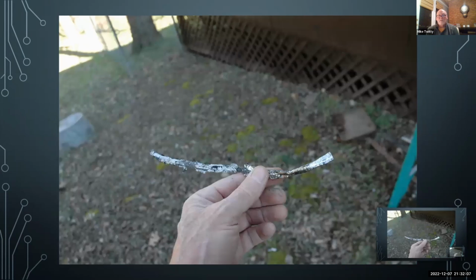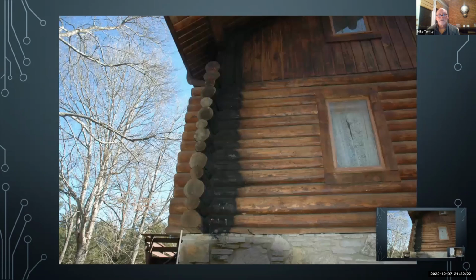The only return path for that neutral current back to the transformer was on the coaxial cable. That's what's left of it. It was traveling on that shield that was carrying all the neutral current of that house back to the transformer, and it melted it down, and it's a wonder it didn't burn the house down. That's where the coax ran up and went into the side of the house on this log house. Very dangerous situation. That's not really to the grounding, but it's showing it's taking another path. It's going to take whatever path is there. The only path there was that coax.